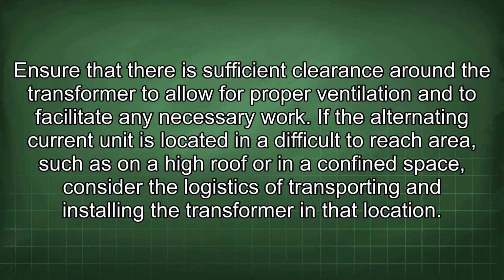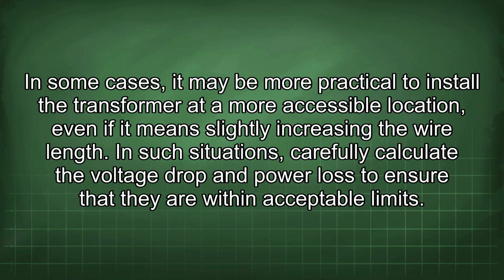If the alternating current unit is located in a difficult-to-reach area, such as on a high roof or in a confined space, consider the logistics of transporting and installing the transformer in that location. In some cases, it may be more practical to install the transformer at a more accessible location, even if it means slightly increasing the wire length. In such situations, carefully calculate the voltage drop and power loss to ensure that they are within acceptable limits.